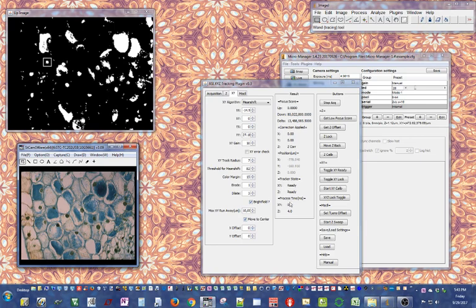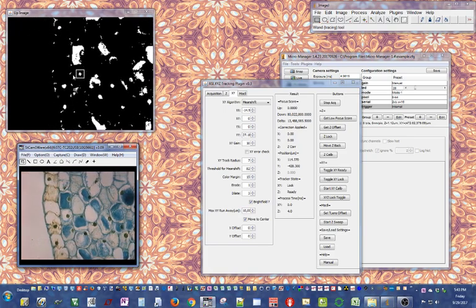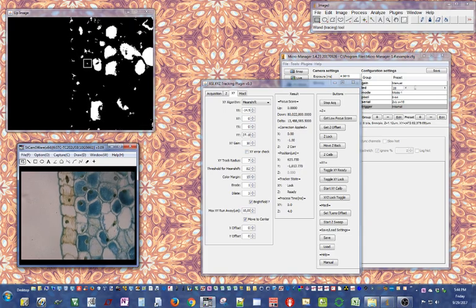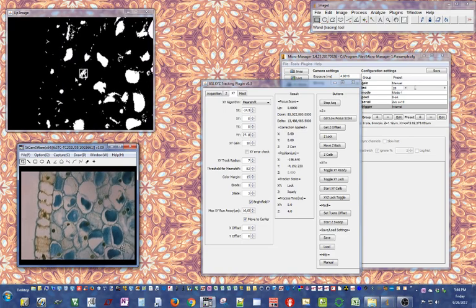In ready state you can see the processing time is barely anything — mean shift is a very fast routine. I right-click to lock and the image is brought to center. Mean shift is pretty robust — I can change the feature I want to track on the fly by clicking a different location. If this were a moving specimen the stage would be moving to keep the sample in view. The stage position display is only updated when in lock state.